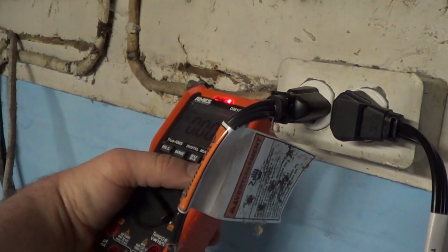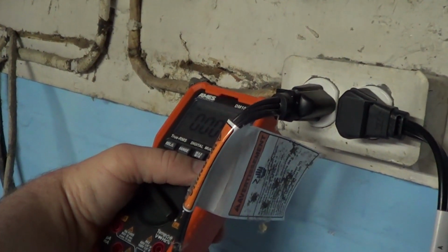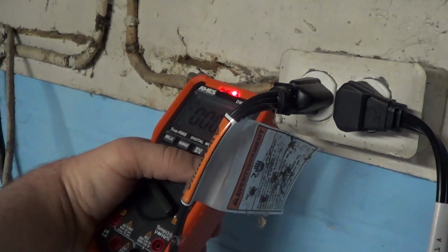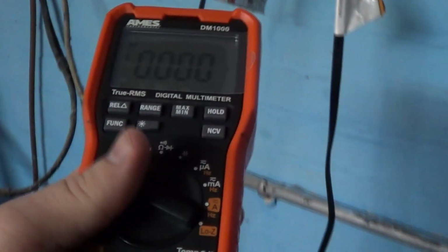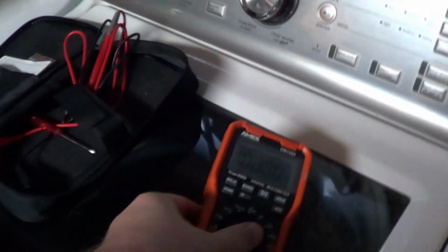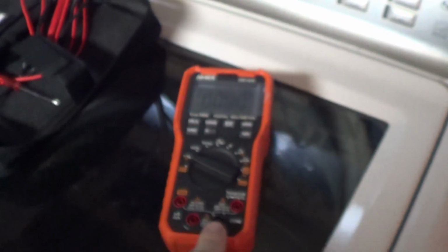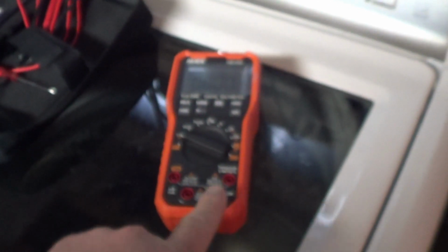If we go out here to this elderly looking wire, here again we have to be almost on top of it, but the measurement does work. Now, some multimeters that have this capability allow for you to take one of the test leads, typically the common test lead, plug it in and utilize it as an external antenna for the non-contact voltage detection feature. The Ames DM1000 does not do that.